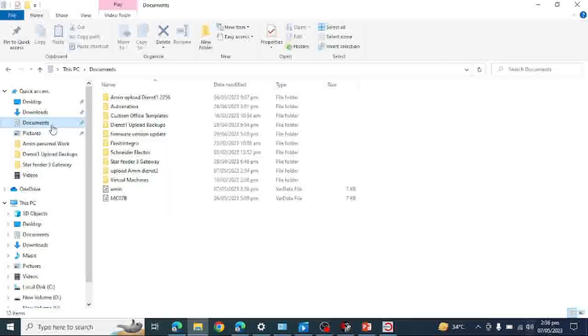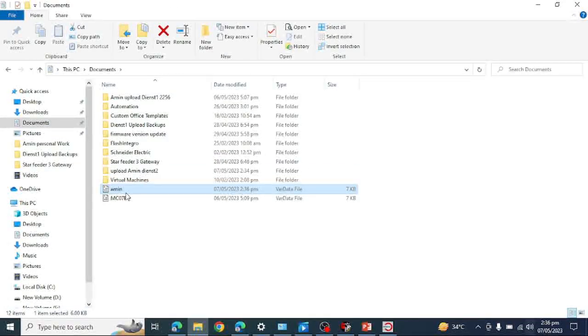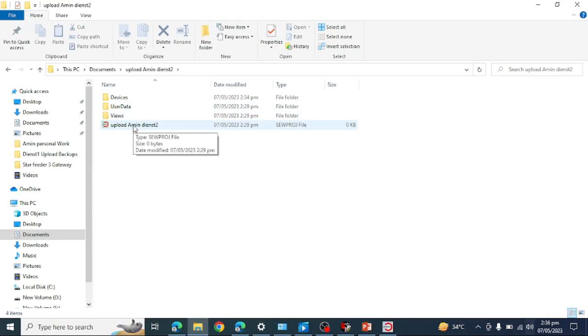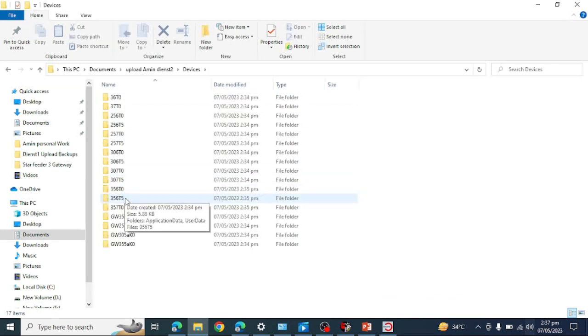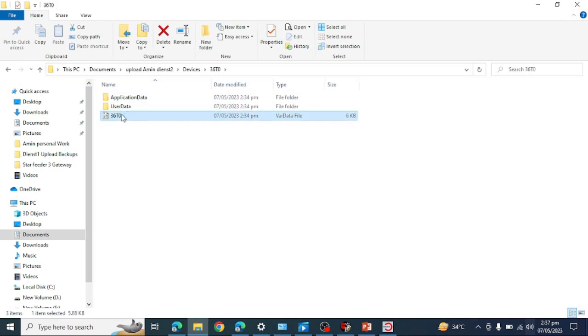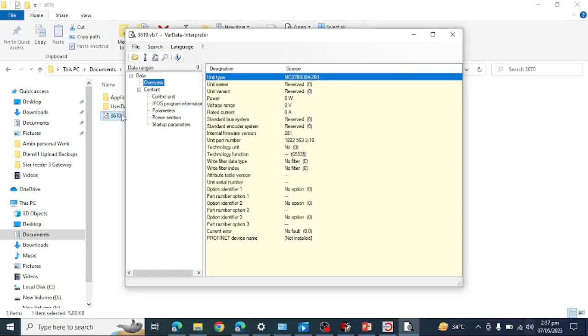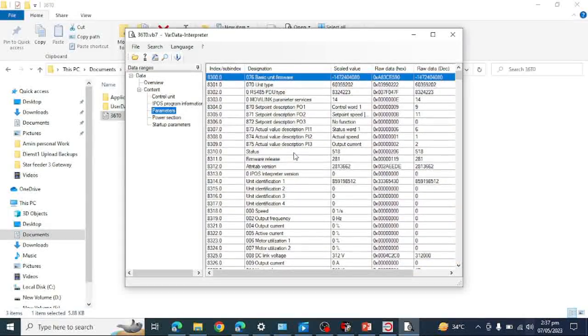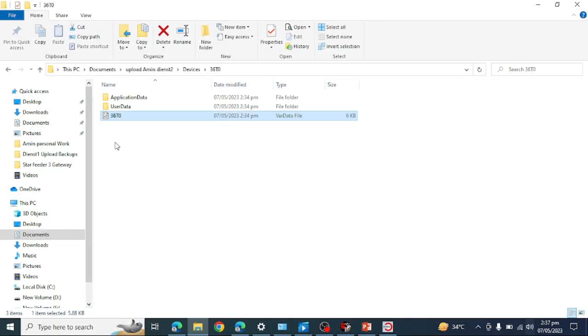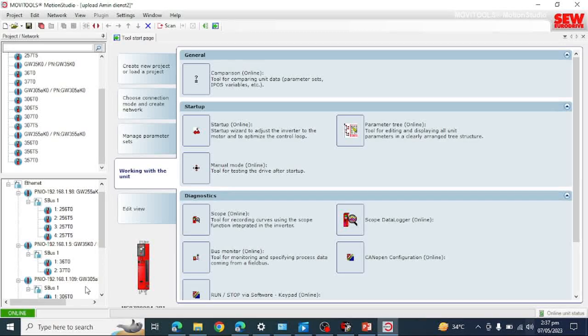Now going to My Documents — here you can see the standalone backup of the single drive. 'Upload Amine' shows the project file. When you open this project file, it will show you all the configured devices you uploaded before. If you want to see all devices separately, it has made a separate folder for each device. From here you can also see its parameters and other properties — it shows the version, the drive model, and if you go to the parameters it shows all the parameters of the drive. This backup can be used for future reference.